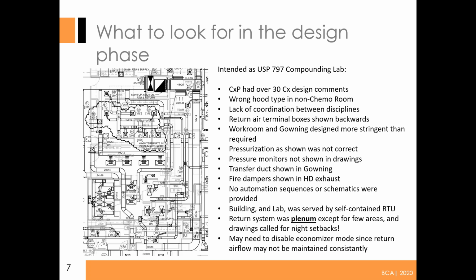So some things to look for: they have the wrong hood type in a non-chemo room. They had lack of coordination between disciplines. This first one I'm highlighting, return air terminal boxes were shown backwards. We had workroom and gowning design more stringent than required. Pressurization was not correct. Pressure monitors not shown. Transfer duct shown in gowning. Fire dampers and the hazardous exhaust. No sequences. I mean, these are kind of common things, but quickly, I'll leave this behind so you can look for some things. When you start looking into these types of rooms, you have to be aware of all the things that can make it fail. Basically, it's not just the amount of air that goes in and goes out.